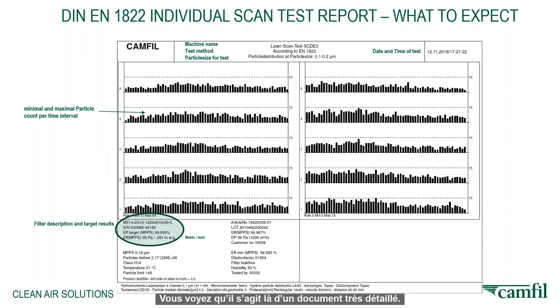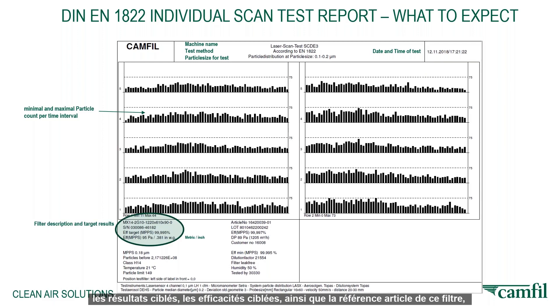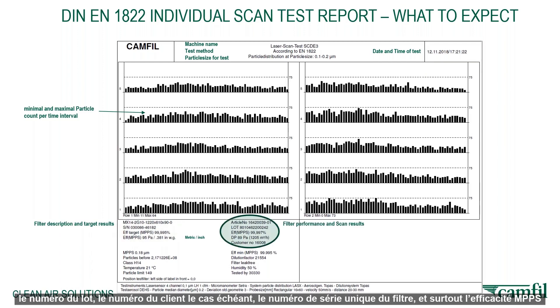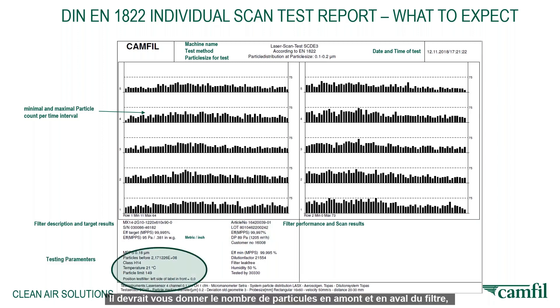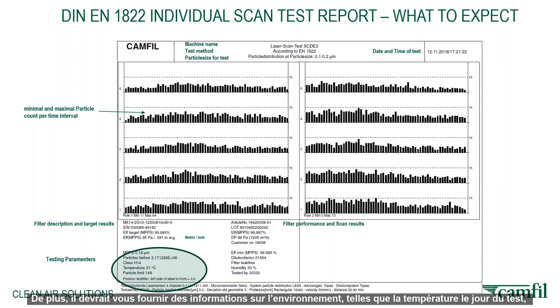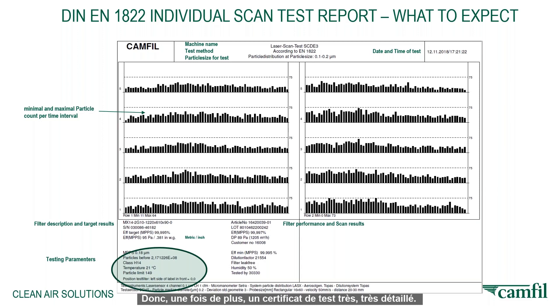It's quite a detailed piece of paperwork. It should give you the filter description, the target results, and the efficiency targets, as well as the article number, the lot number, the customer number if relevant, and a unique serial number for that filter. Importantly, it must include the efficiency at MPPS in order to determine the filter classification, and the number of particles before and after the filter to give you the filter class. It should also include environmental information such as the temperature on the day of the test, the position of the test filter, and items unique to that filter.